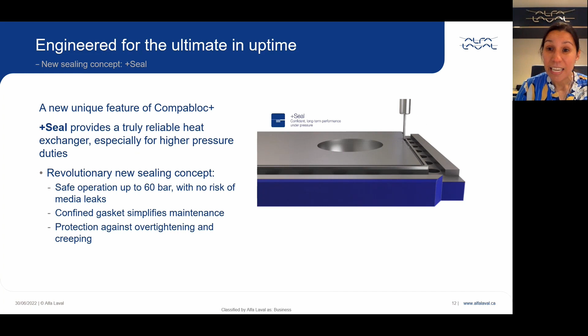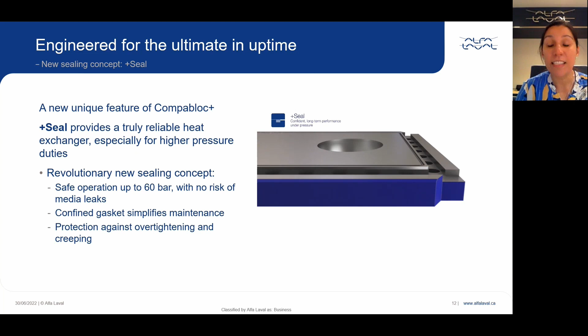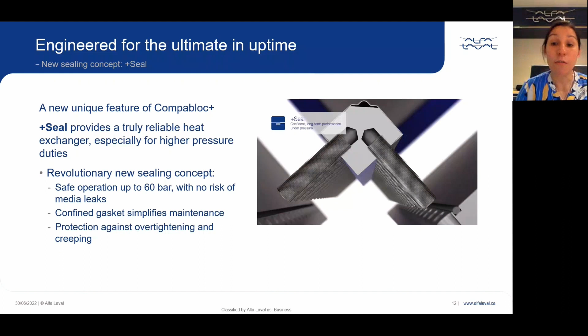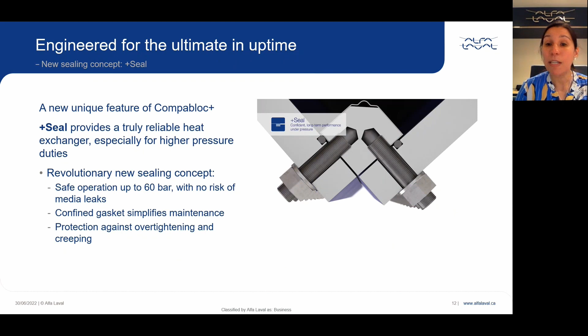So Alfa Laval has developed a new sealing concept which is called the plus seal. You can see it on the screen right now. For the plus seal, we have created a gasket groove, and in this design the gasket is confined inside that groove. It works two ways. The groove protects the gasket from crushing, which can happen when you over tighten the heat exchanger, but it also provides metal to metal surface contact. That also provides a better seal for high pressure applications.